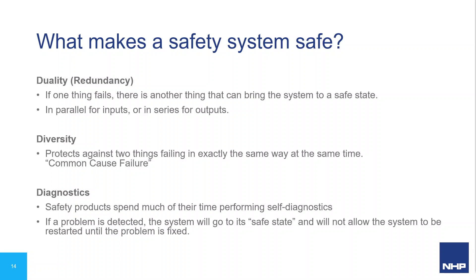Diversity ensures that multiple devices operating in a redundant system don't all fail from the same fault. For example, if two switches from the same batch and manufacturer have an anomaly where they fail dangerously under a high voltage spike, they could fail simultaneously in a power surge. Whereas if you have two sensors from different manufacturers or different types — one electromechanical, one solid state — the likelihood of the same fault damaging both in the same way at the same time is greatly reduced.